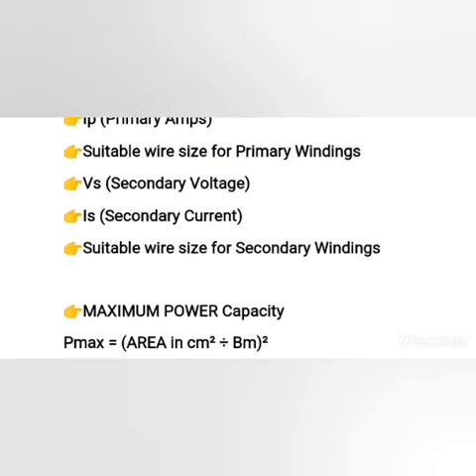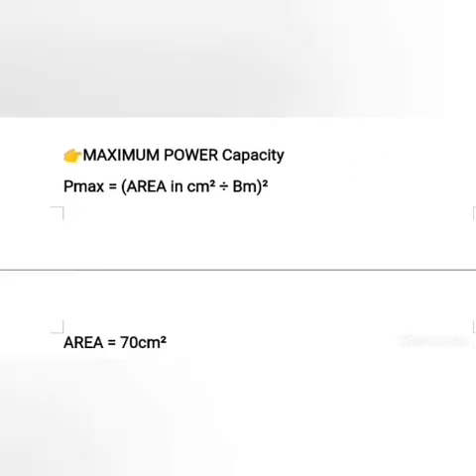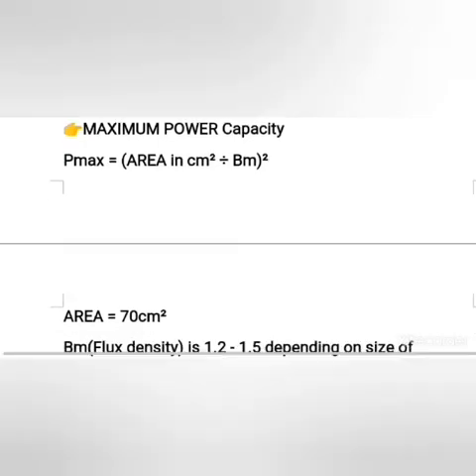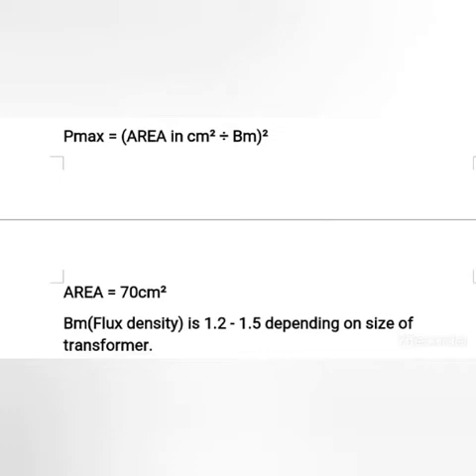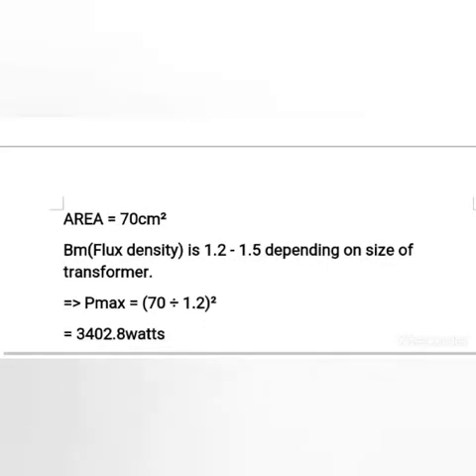The first on the list is the maximum power capacity of the welding transformer. The formula is: maximum power equals area in cm squared over flux density, all squared. We have our area at 70 cm squared, and the flux density range is usually between 1.2 to 1.5 depending on the size of the transformer. Using 1.2 for this particular welding transformer, maximum power equals 70 over 1.2, all squared, giving us approximately 3,400 watts — so 3.4 kilowatts.